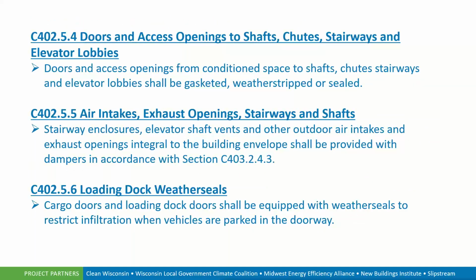There are also sections in the code that pertain to shafts or chutes, stairways, and elevator lobbies, making sure that those doors are gasketed properly, weather stripped, or sealed. We have air intakes, making sure that those air intakes or exhaust openings are integral to the building envelope and have dampers in accordance with C403.2.4.3 that will allow that airflow to be shut off.